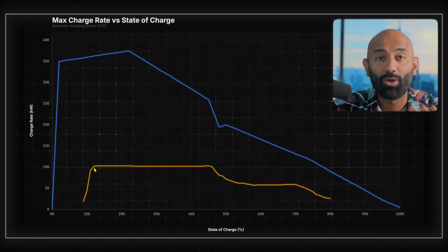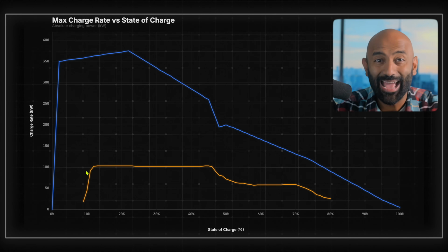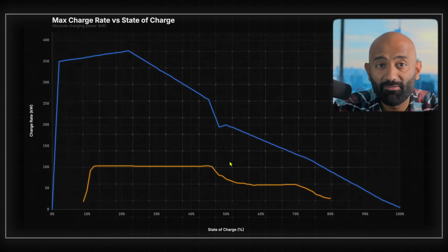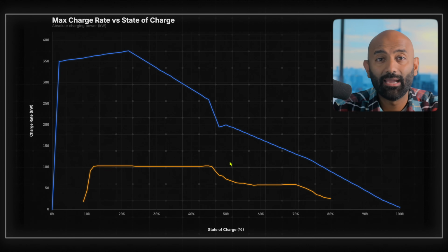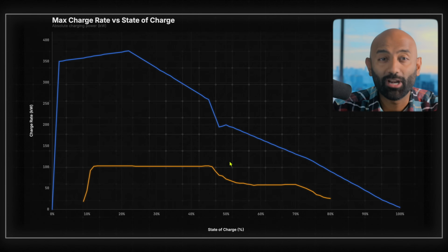Within a minute, the pack ramps up to 103 kilowatts, a 5.7 C charge rate at the pack level, and held it flat for nearly 5 minutes. And that got the pack from 10 to 50% in about 5 minutes, 10 to 70 in 9, and 10 to 80 in 12 minutes, which is incredibly quick.